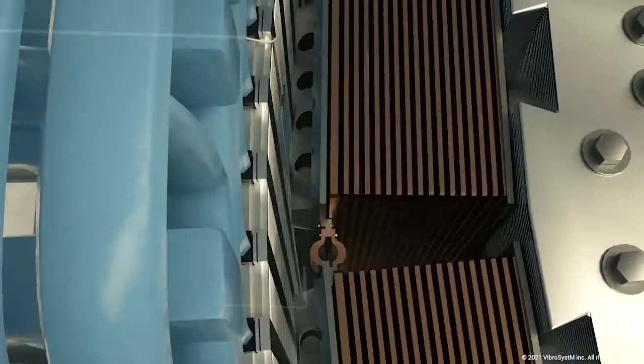So they had 4 units at this power station. They were building them. And the OEM that won the bid had a new design. Well, at that time, it was a new design. And the design was that the rotor rim was a shrink fit rim. But if the unit ever went beyond 110% speed, the rim would be allowed to move around, what we call floating around, to absorb the centrifugal forces.